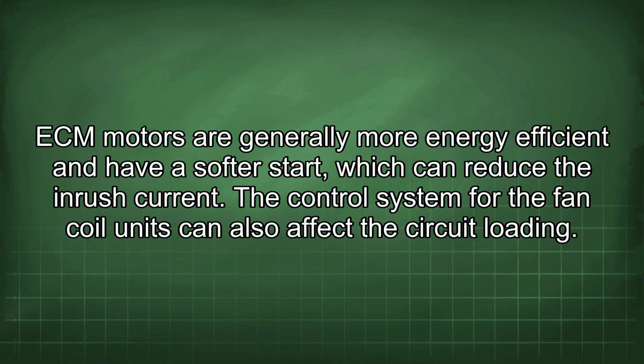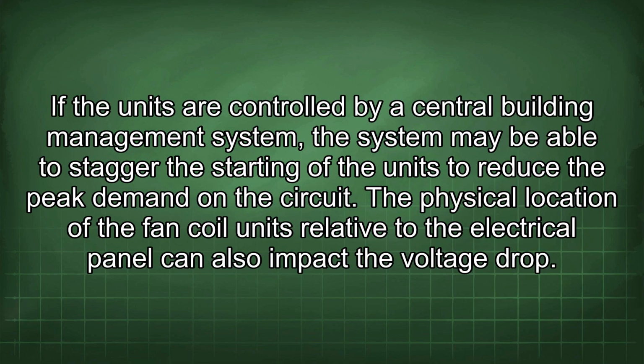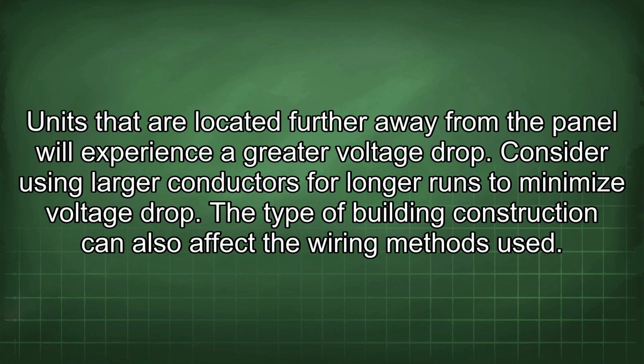The control system for the fan coil units can also affect the circuit loading. If the units are controlled by a central building management system, the system may be able to stagger the starting of the units to reduce the peak demand in the circuit. The physical location of the fan coil units relative to the electrical panel can also impact the voltage drop. Units that are located further away from the panel will experience a greater voltage drop. Consider using larger conductors for longer runs to minimize voltage drop.